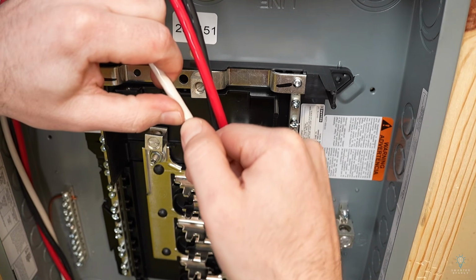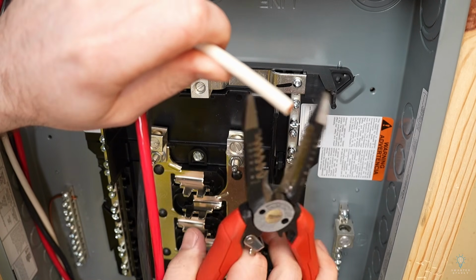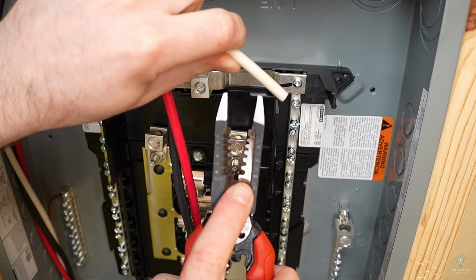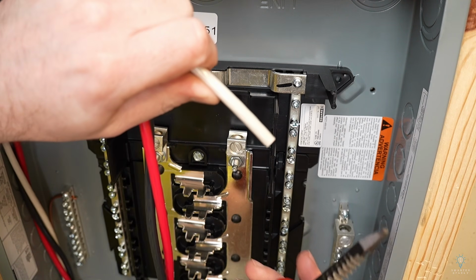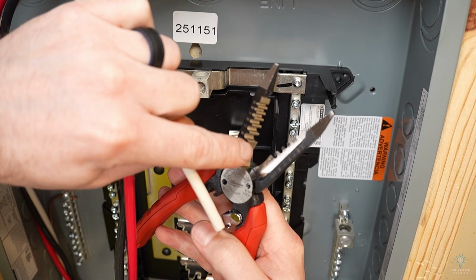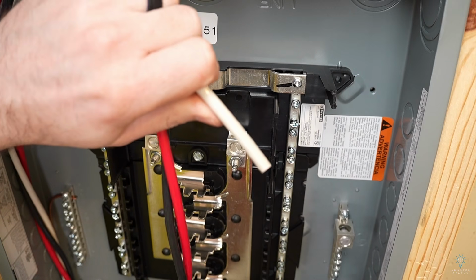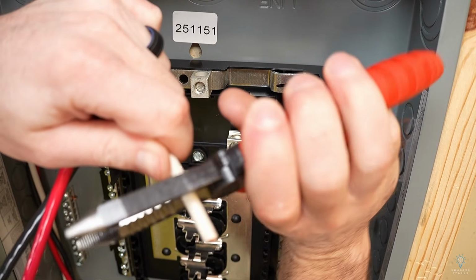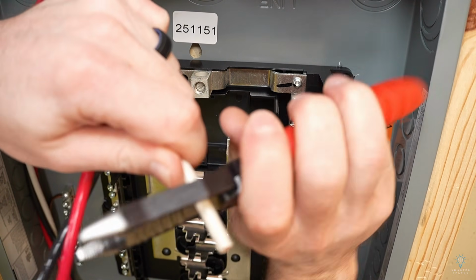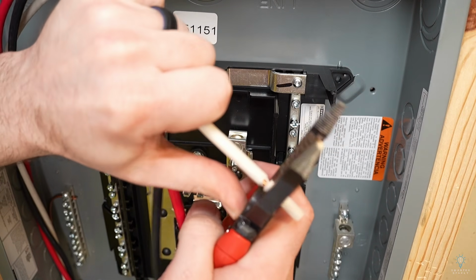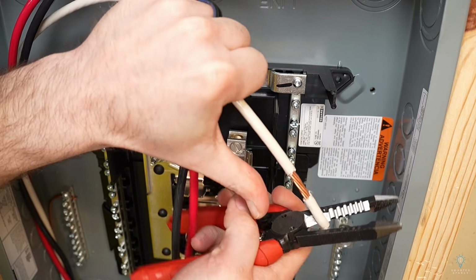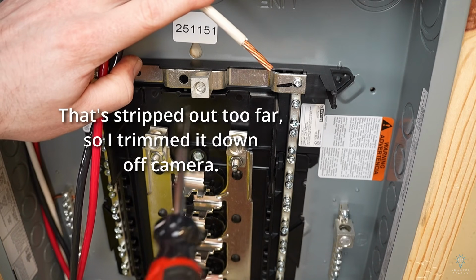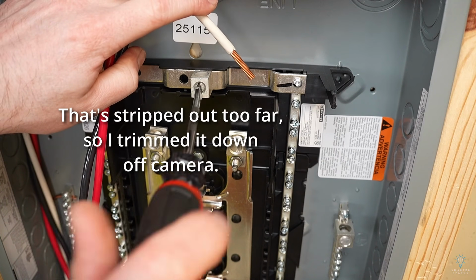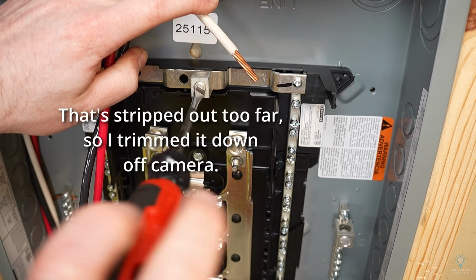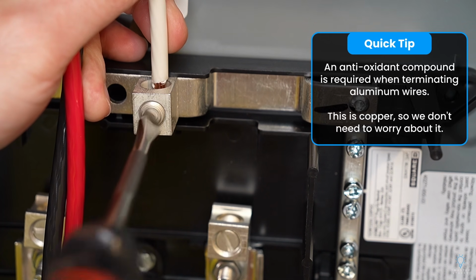So I'm going to cut it right here and strip it out. Now my strippers only go up to 10-gauge wire, and this is 6-gauge wire. So I'm actually going to score it very lightly with the wire cutting portion of the strippers, and that will allow me to then remove the insulation like so. And then we can install the neutral. And then we can go ahead and tighten that neutral down.